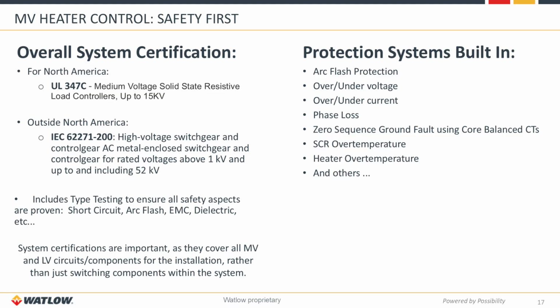This would cover the systems that we're talking about and is a complete system standard, meaning it goes through the enclosure, the wiring, the switching devices, the protection schemes. It covers the entire system to ensure the system is reliable and safe within the application. Same thing with the rest of the world. Outside of North America, IEC 62271-200 is the high voltage switchgear and control gear for AC metal enclosed switchgear and control gear rated for voltages 1 kV to 52 kV. Again, our systems would fall under that particular standard for the rest of the world.